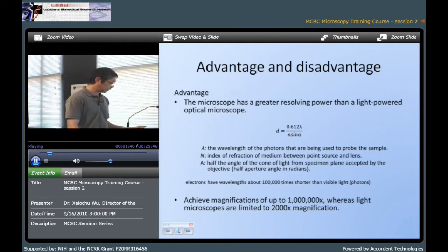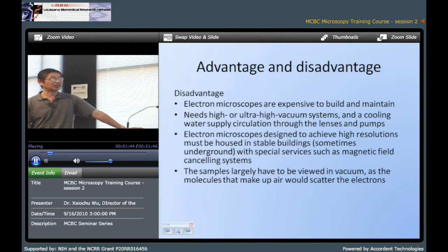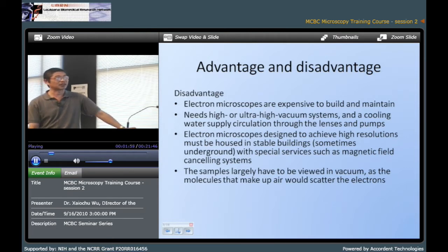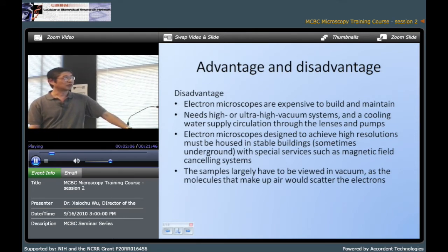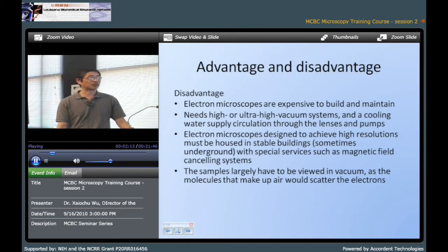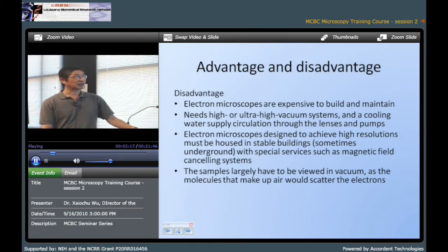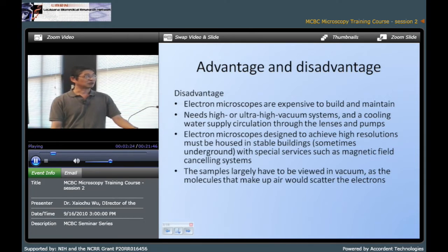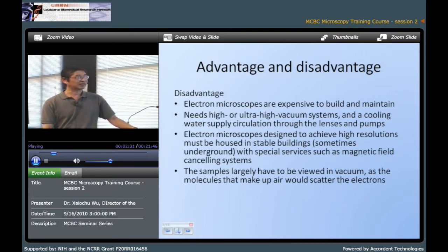Of course electron microscopy also has its disadvantages. For example, electron microscopy is very expensive to build and to maintain, and we need to use high vacuum to eliminate scattered electrons. Also, electron microscopy needs a cooling system to cool the lens and pumps. Because electron microscopy has high resolution, you need to mount it on a very stable place to eliminate vibration, and also it needs to eliminate the magnetic field.